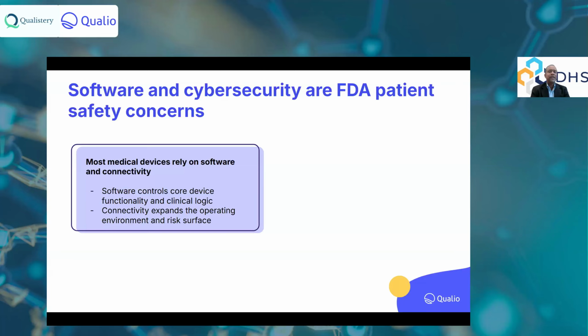I'm not sure about that answer. Like I mentioned, my team does hazard analysis and DFMEA both for the reasons I spoke about. So that has been our go-to process. We have always been leveraging 13485 even for FDA-regulated products because it's more comprehensive, and allows our clients to take our deliverables at DHF not just for US submission, but worldwide submission as well, right? So we always were aligned in our journey on all our projects with 13485. So specifically for us, I would not expect our process to change.